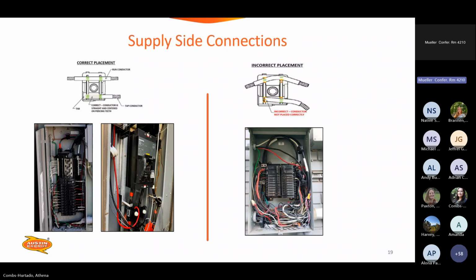Okay, so supply side connections again. You can see those two pictures on the top there are taken from a manufacturer explaining how to do a tap properly. You want to have a straight piece of conductor so that connection can be safe and lasting. We also have some good pictures on the left of supply side taps that were done properly. There's plenty of room in those panels. They are done on a straight piece of service conductor. Picture on the right, however, if you look closely on the right of that panel, you can see those piercing taps are done. There's just not enough room there.